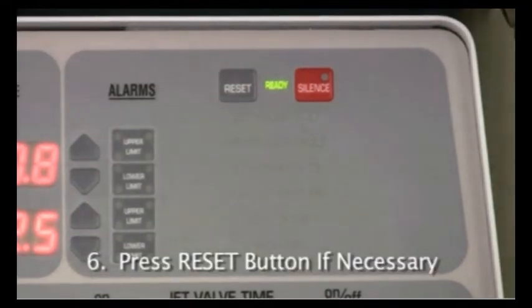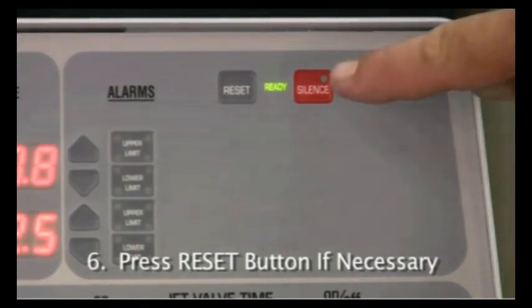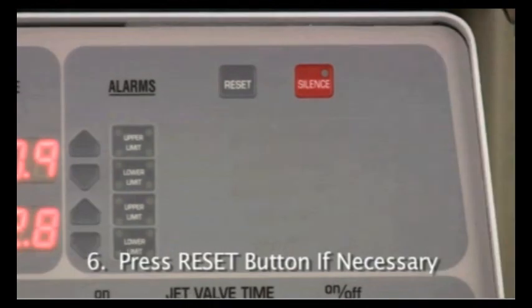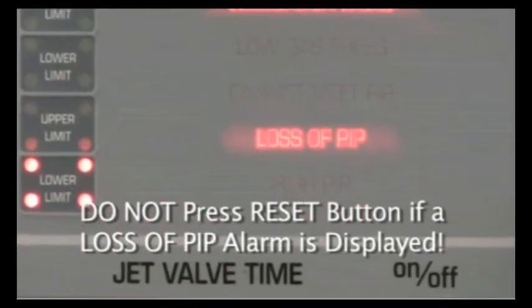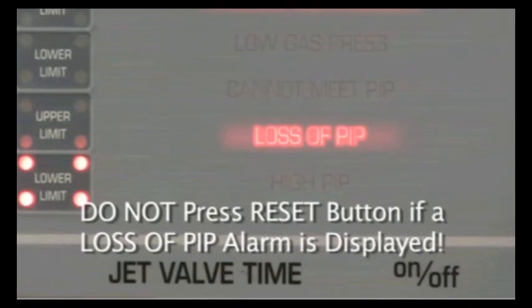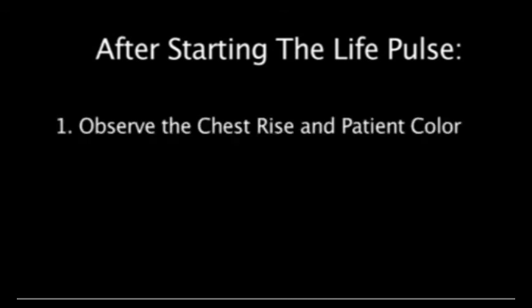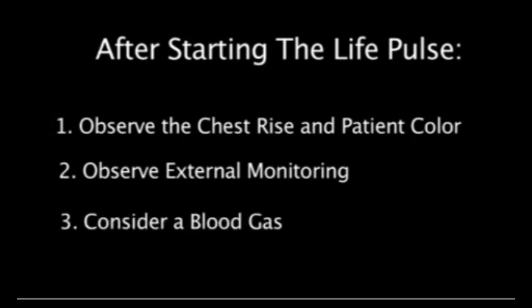Six, after settings have stabilized, if a mean airway pressure alarm occurs, press reset to allow the LifePulse to recalculate correct alarm limits around the new settings. Do not press reset if there is a loss of PIP alarm displayed in the alarm section of the LifePulse. And that's really all there is to starting the LifePulse on a patient. At this point, just do the things you normally do when you start a ventilator on a patient. Observe the chest rise, examine the patient's color, look at the oximeter, possibly get a blood gas. All the things you would normally do when starting a patient on a ventilator can now be done with the LifePulse.